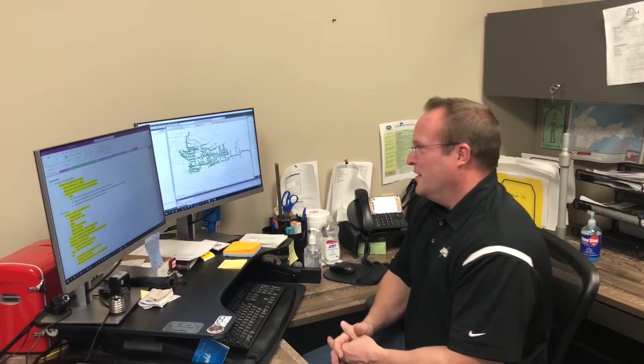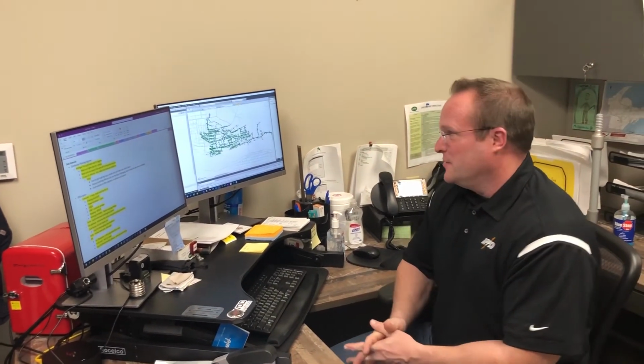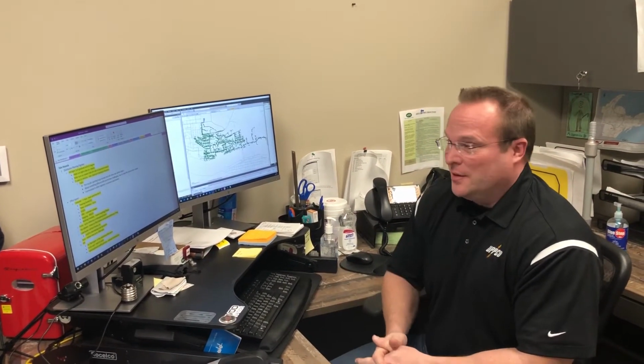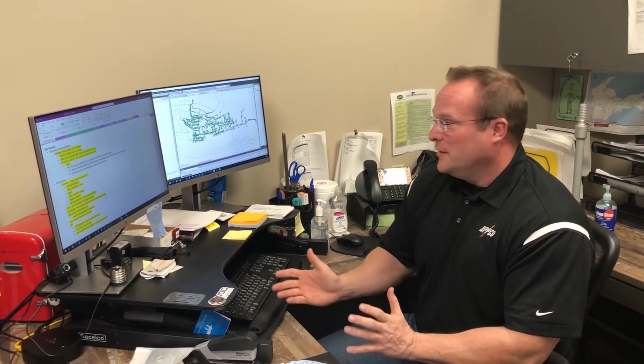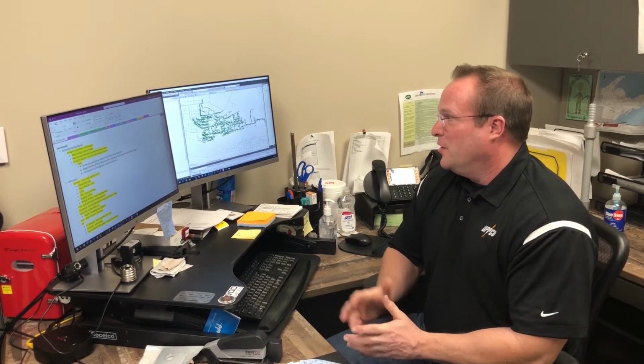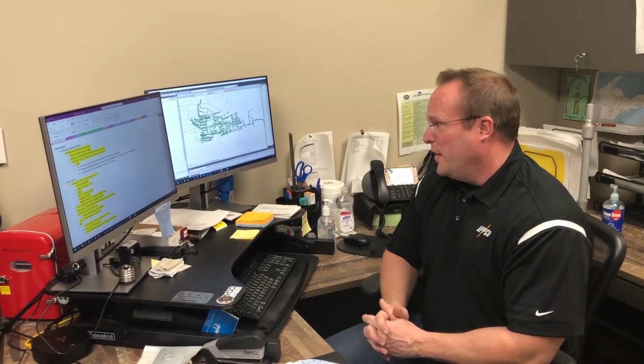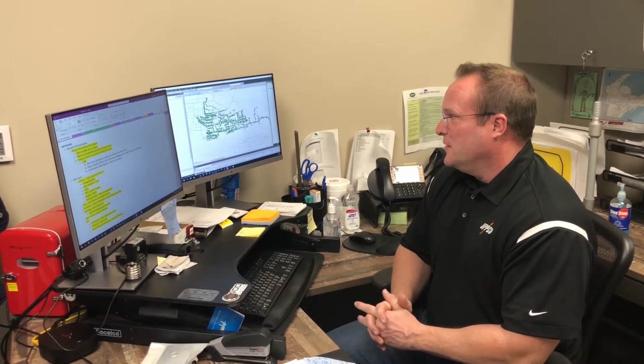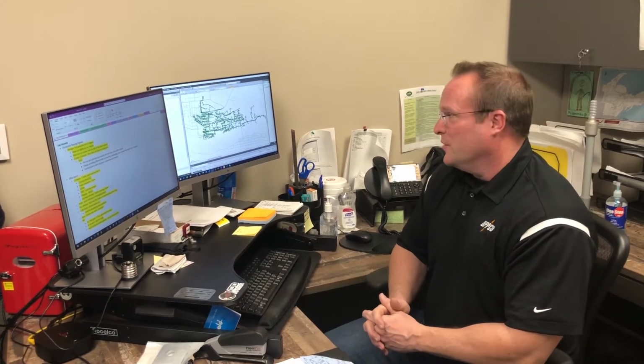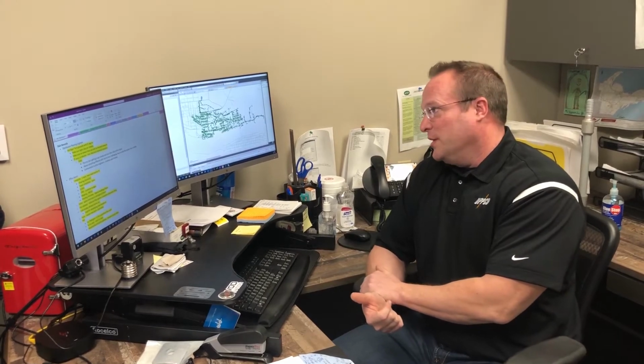Another tool on the computer that the engineers use is the CYME. In this case, it's a power simulation software that we use to simulate the network and test out conductor sizes, fuses, whatever you may, and enables us to add a portion to the circuit and test out if the circuit's going to respond the way we want. And also for coordination between the substation and all the downstream devices to make sure in the event of a storm or a tree down on the line, it's not going to knock out all the power for that particular line, and isolate the storm as much as possible.